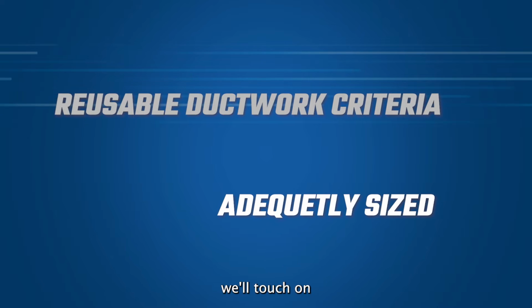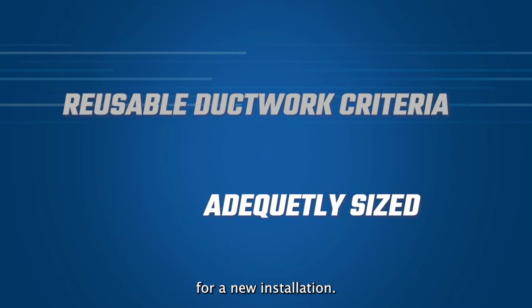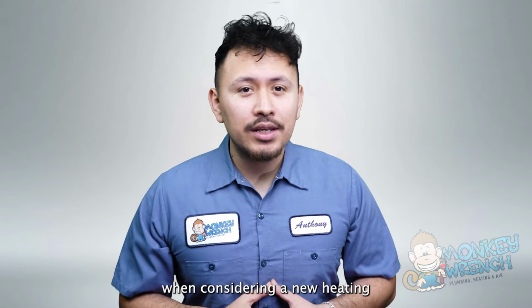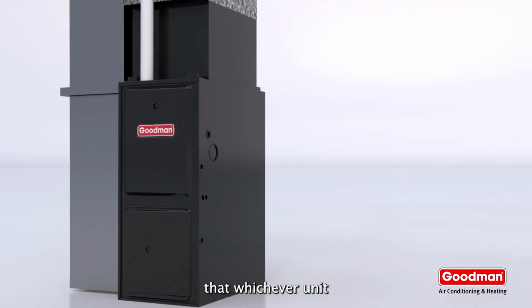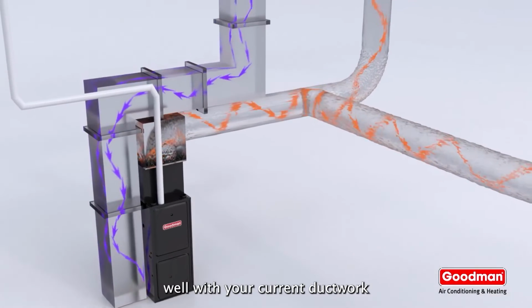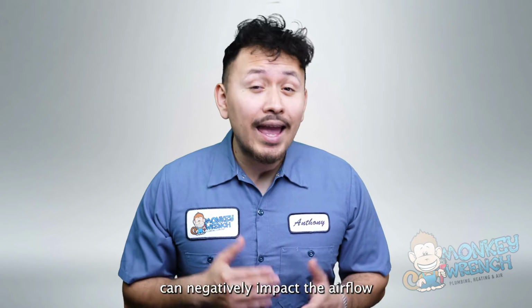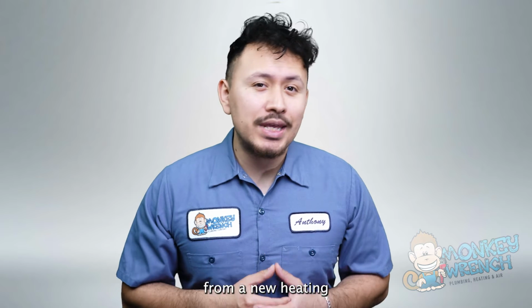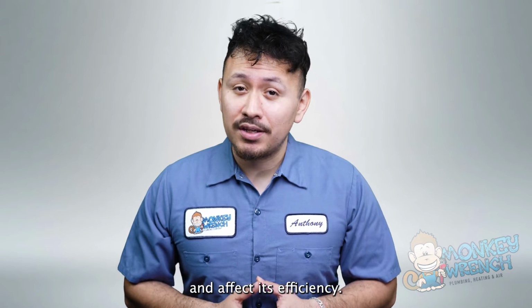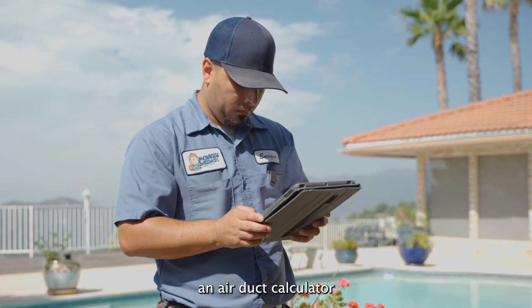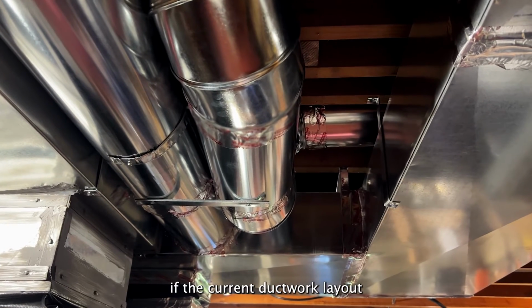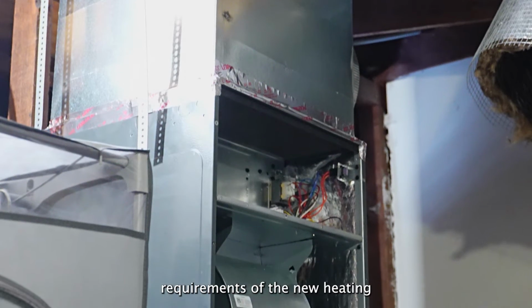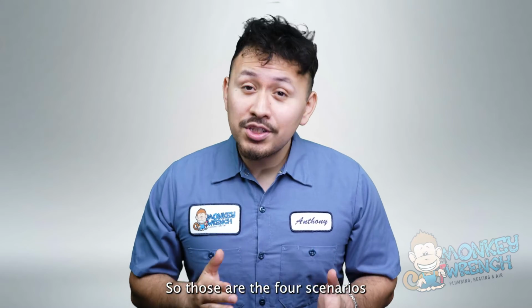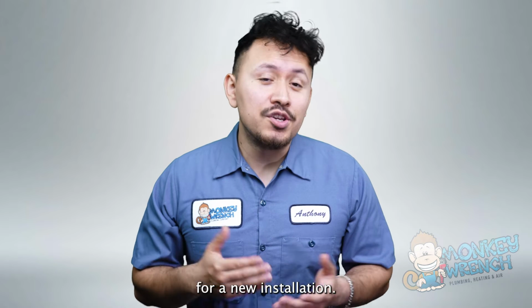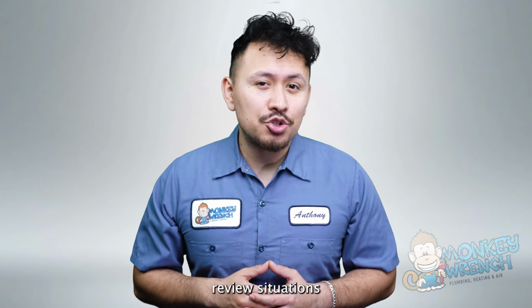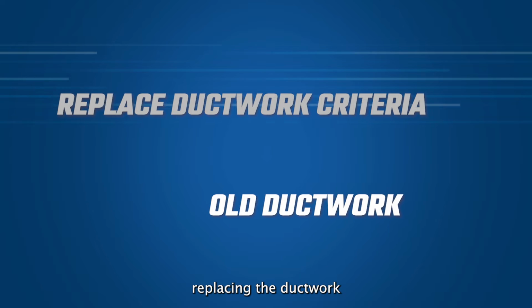One last scenario we'll touch on is ensuring the ductwork is rightfully sized for a new installation. When considering a new heating and cooling system, it's key to ensure that whichever unit you choose fits well with your current ductwork. Over or undersized ductwork can negatively impact the airflow from a new heating and cooling system and affect its efficiency. To avoid this, technicians use an air duct calculator to determine if the current ductwork layout meets the new duct requirements of the new heating and cooling system. So those are the 4 scenarios where you may keep the current ductwork for a new installation. Now, we're going to review situations where it's best to consider replacing the ductwork instead.